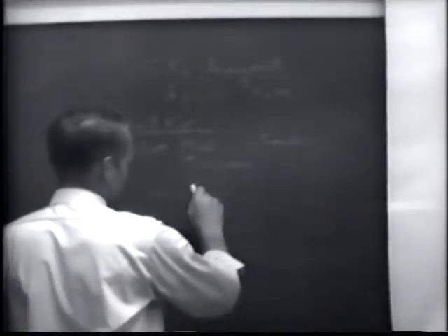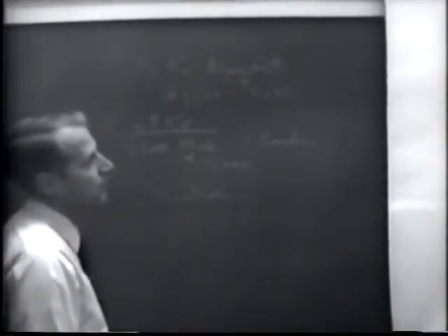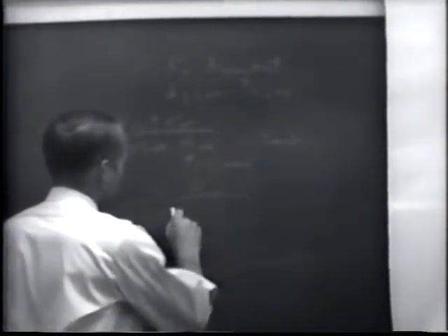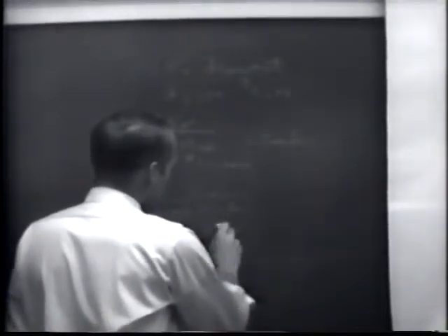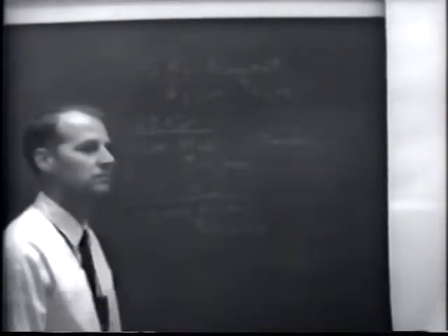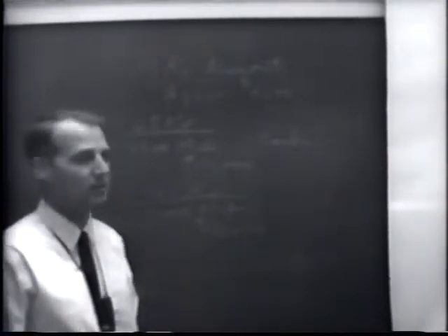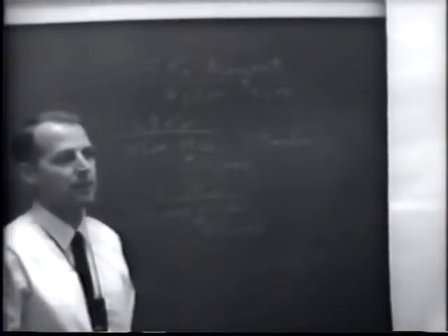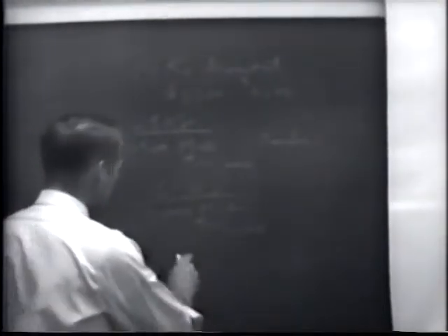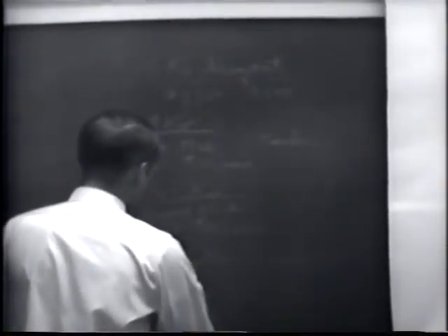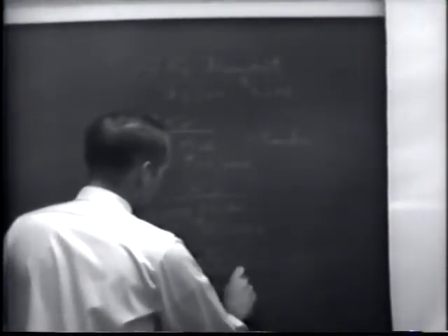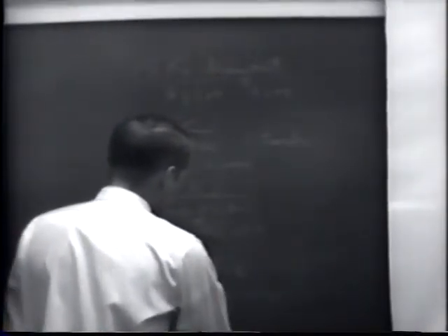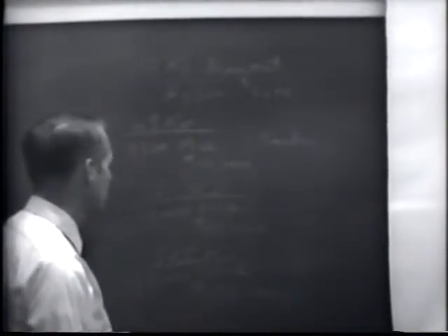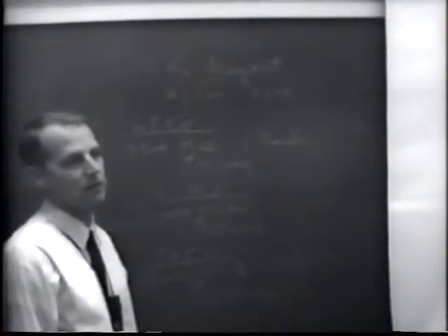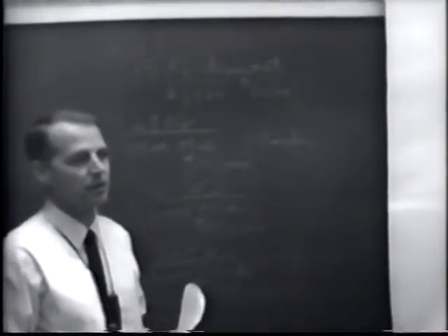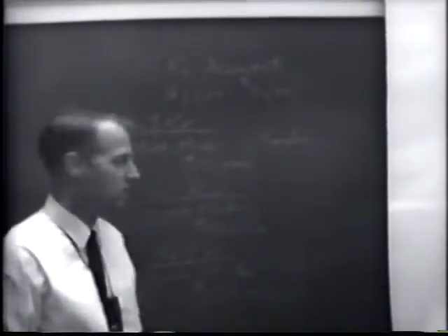The 161 kV breaker price here is in the order of $40,000. This can vary a little bit below that to maybe $3,000 or $4,000 above that, depending upon how many circuit breakers you buy at one time and what the market price is. And then to go up to our 345 kV, 25,000 MVA breaker, that's $150,000. So you can see the price goes up rapidly as we go up in voltage and interrupting capacity. And this is just the price of the breaker alone. It doesn't include the installation, it doesn't include all the protective equipment that's necessary to control this circuit breaker.